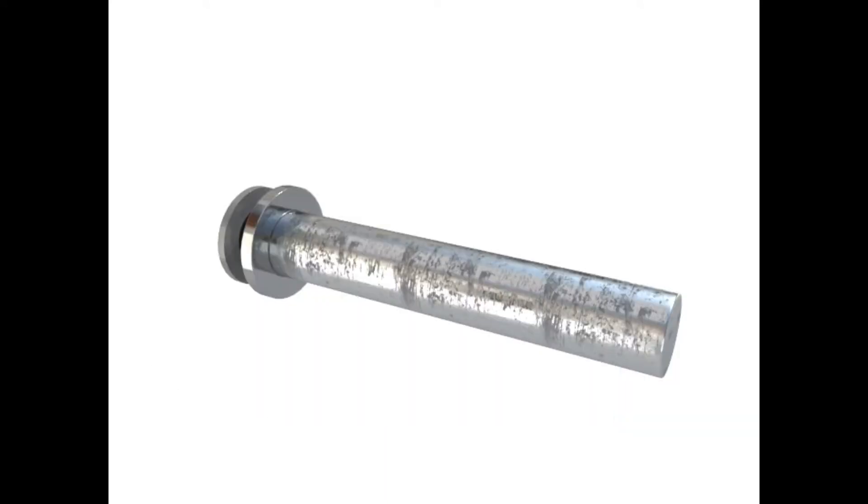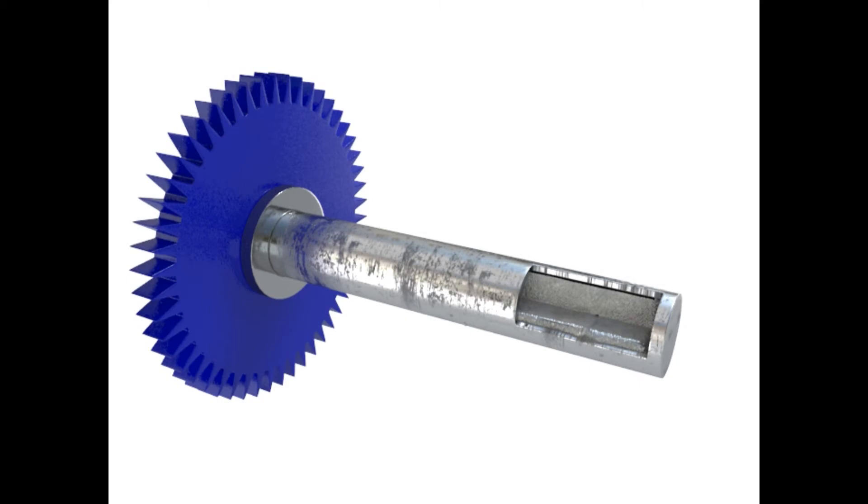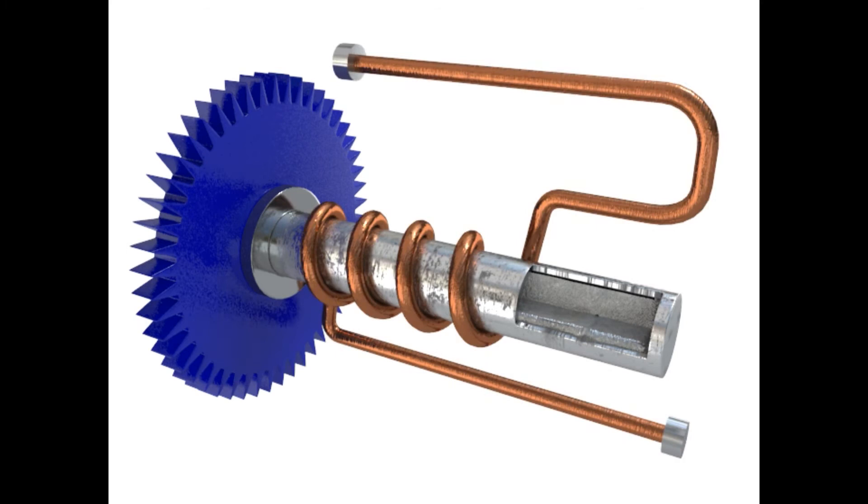In a melting alloy overload relay, the eutectic alloy is housed in a tube along with an inner shaft cemented in place. This tube is connected to a ratchet wheel. The temperature of the alloy is controlled by a heater coil wrapped around the outside of the tube. The heater coil is directly connected to the circuitry of the motor, so when dangerous amounts of current run through the motor, the wire coil will also heat up.